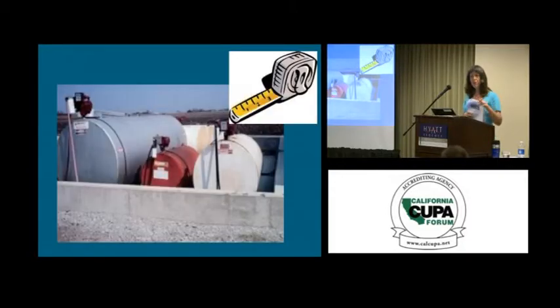So what we're talking about here are our bulk tanks, and this is where a facility is required to construct their containment for bulk storage and drums. That includes drums, bulk storage containers, and tanks, so that you provide a secondary means of containment for the entire capacity of the largest single container and sufficient freeboard to contain precipitation. And that's right in that section. Dikes, containment curbs, and pits are commonly employed for this purpose, and then we'll talk about alternatives later.